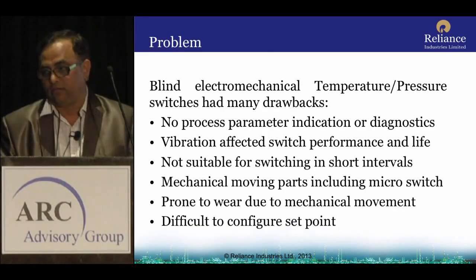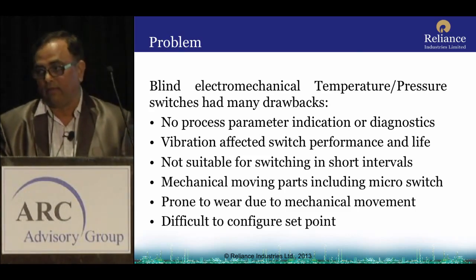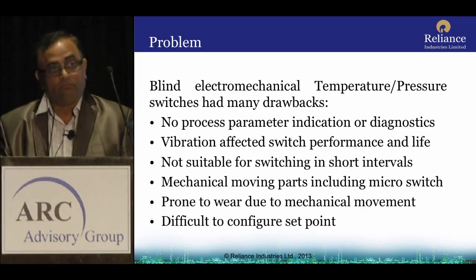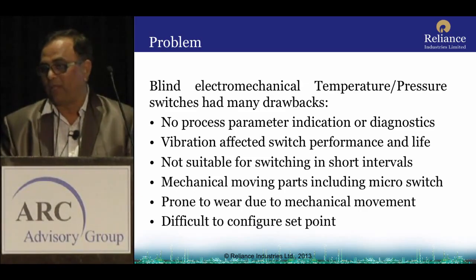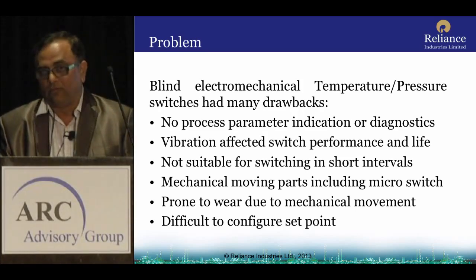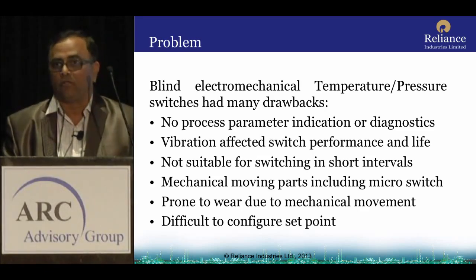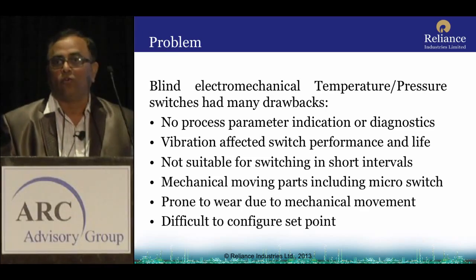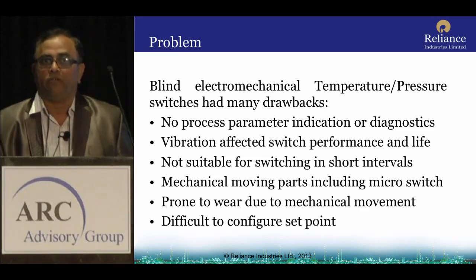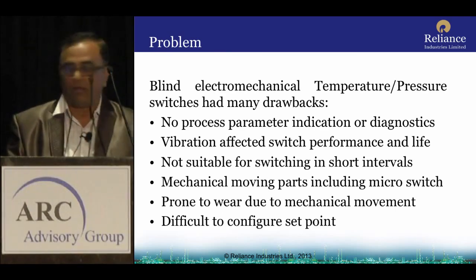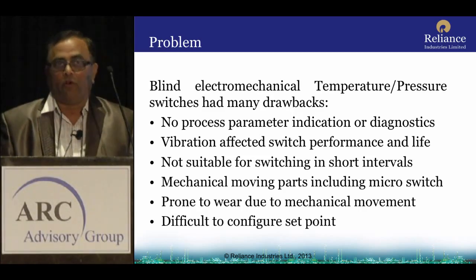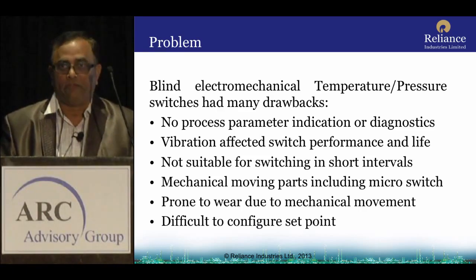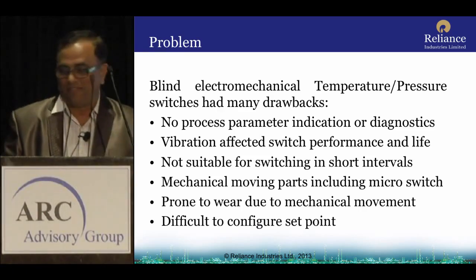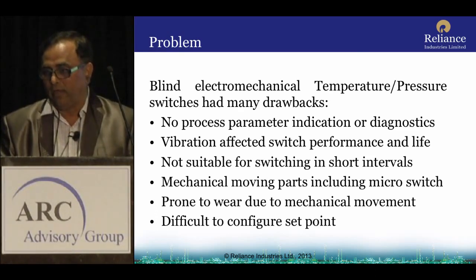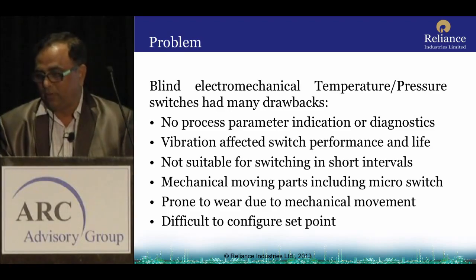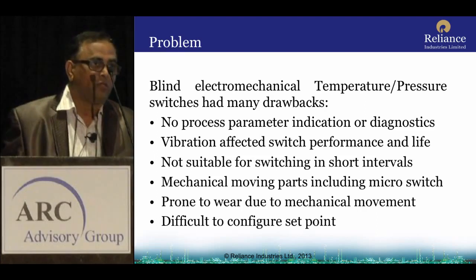Now, the problem statement is that we had blind electromechanical temperature and pressure switches. The drawbacks: no process parameter indication or diagnostics on the mechanical switches. This application is on a reciprocating compressor, which has its own inherent vibrations, which result in drifting of the set points of the electromechanical switches. So, if you want switching at short intervals, it is difficult. There are mechanical moving parts including the micro switch, prone to wear due to mechanical movement, and difficult to calibrate or configure the switch in a short time.